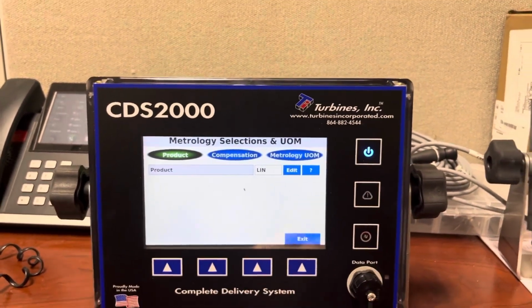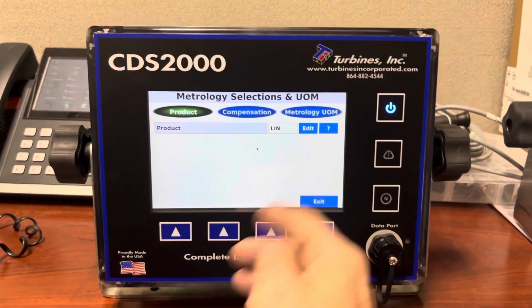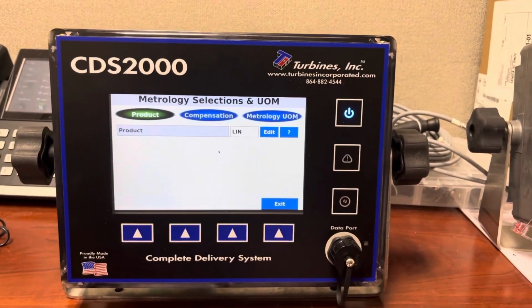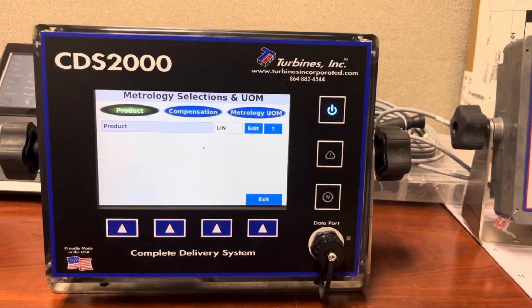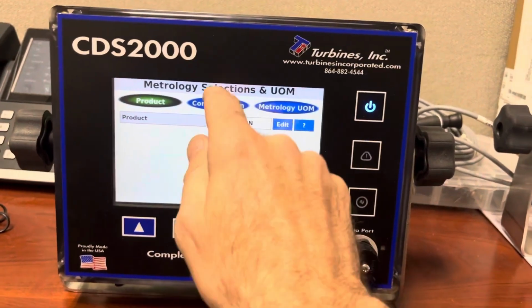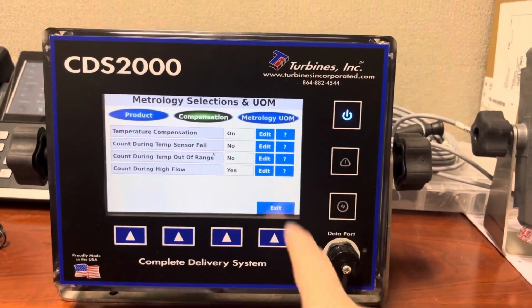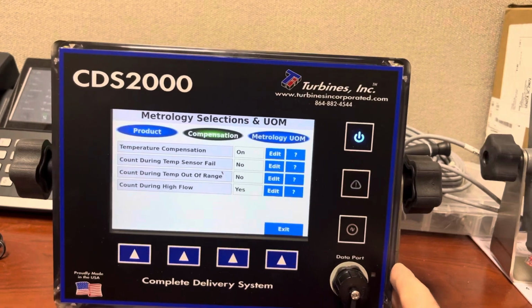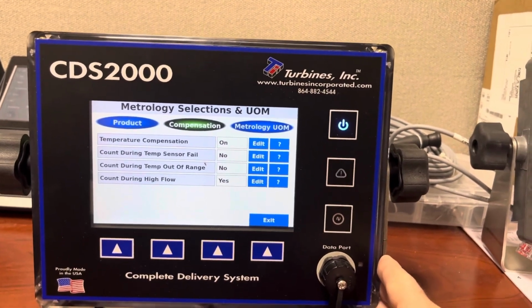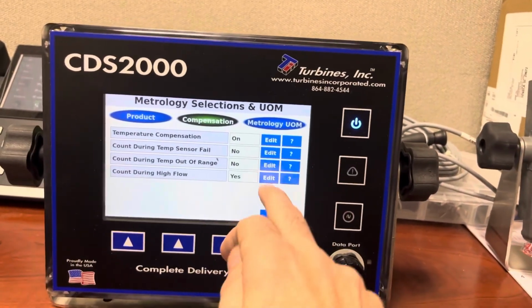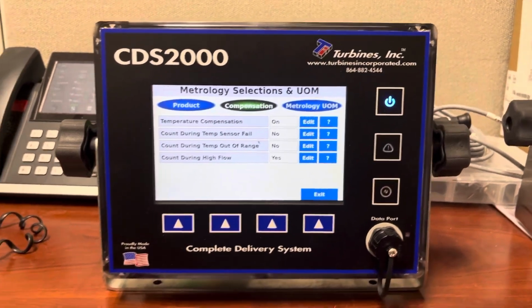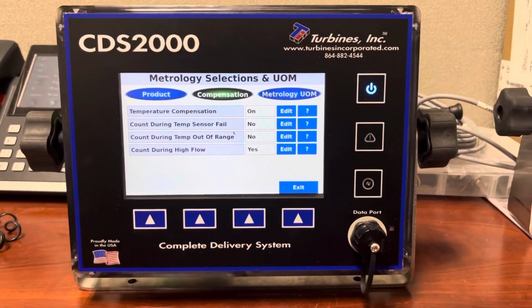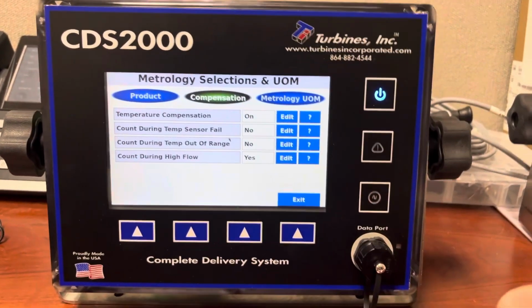So the things that you're going to want to change, depending on the service it goes into, you may need to change from Lin to LOX or to argon. Compensation is next. You always want your temperature compensation on, count during temp sense fail off, count during temp out of range off, and count during high flow. That's up to you. Some people like to have it. You shouldn't ever high flow these meters. You can leave it on or off.